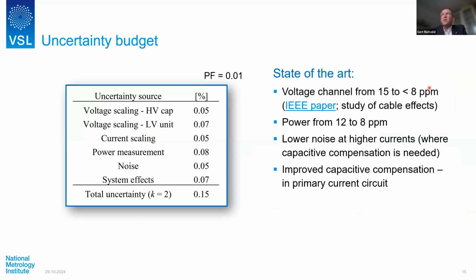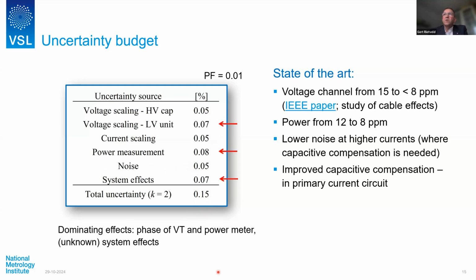Looking at the uncertainty budget, you clearly recognize the 3 components: voltage scaling, current scaling, power measurement, and then there's, of course, the total system. You have noise in the system. You will not be able to have, say, negligible noise in your current phase angle generation. We are now able to do it with a few ppm, a few microradians really, but there's still a noise contribution of a few ppm. But if you add them all up, they're at the level of 0.15% at power factor 0.01. And you see the main components are comparable. I mean, we have voltage scaling, and power measurements are less accurate than the current scaling.